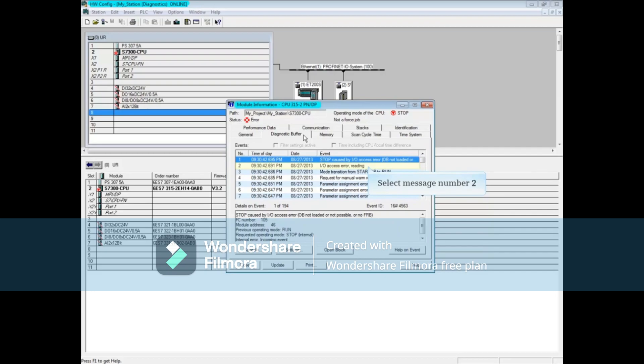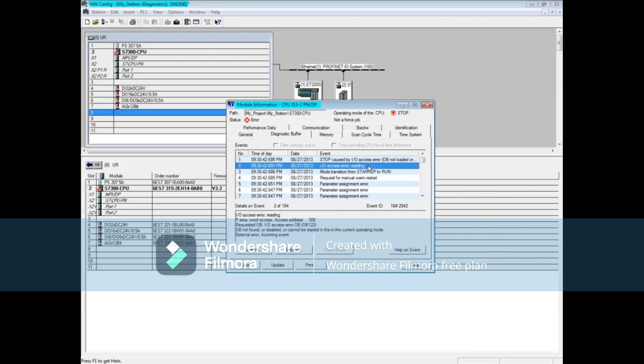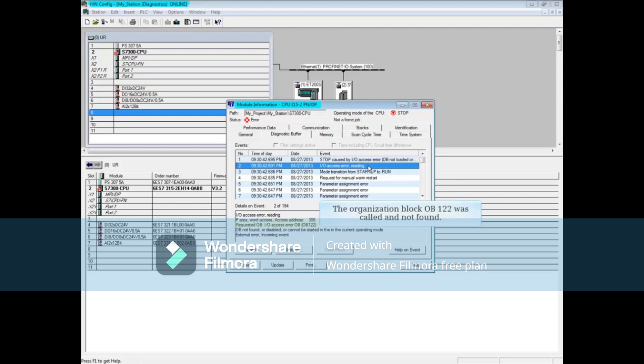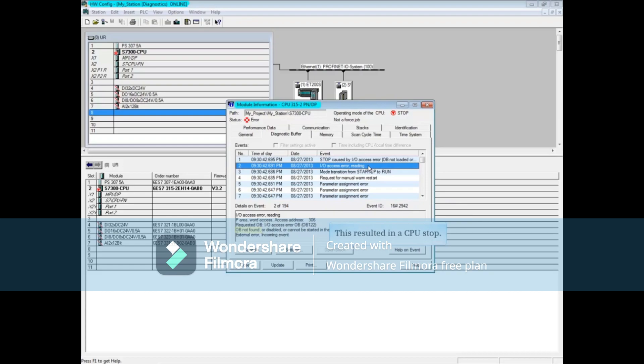Click message 2 for more information. In the details of the event, the message says there was an I.O. access error when reading. An attempt to read the P or peripheral area word access address with address 306. Also, the organization block OB122 was called for and was not found. This resulted in a CPU stop.